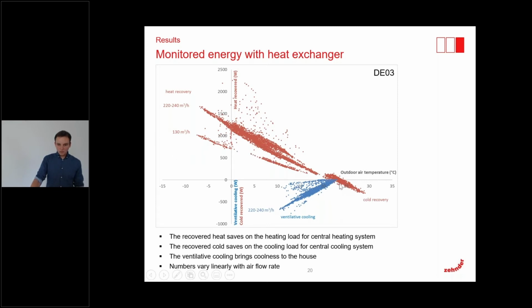And in summer, this is also shown by the red dots. We can see the cold recovery. Here we are using the heat exchanger to get the cold from the extract air to the supply air. And the blue dots show the energy brought by ventilative cooling.